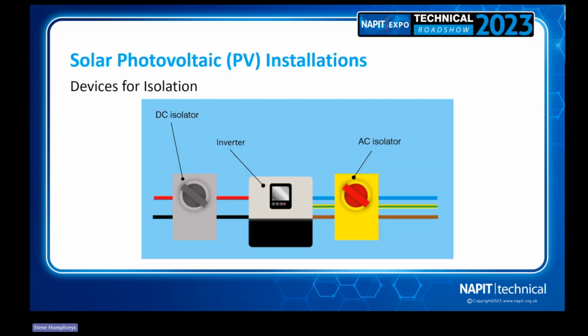Big one in the industry at the moment that's causing a lot of noise for those that are installing these kind of systems, you might have seen it, is isolation, especially DC isolation. So again, what the regs do tell us in 712.537.2.101 is that we do need to have a means of isolating the DC side from the inverter. So this is to facilitate maintenance, or perhaps swapping out the inverter as a whole, whatever that may be. So that's why you've got your DC isolator there.